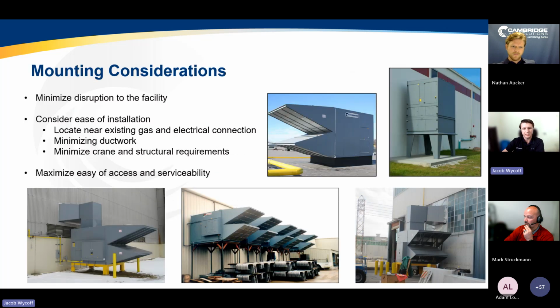Another thing to think about is where are you going to put this unit? So in most of these industrial retrofit applications, we're really thinking first about minimizing the disruption to the facility. That square footage inside is extremely valuable, and we want to let the facility have that space to do their manufacturing. So typically this results in mounting the unit outside. This is great. You want to consider the ease of installation as well. If you have an existing unit, you want to locate the new unit near the existing gas and electrical connections if possible.